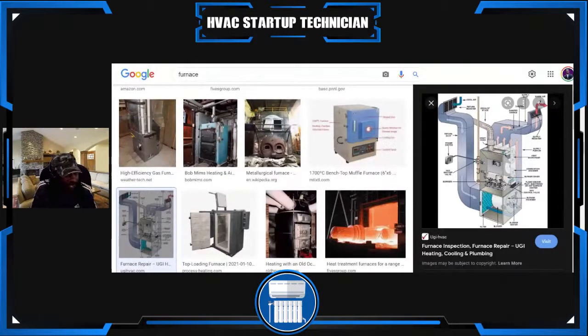And then again, you're still looking at your manual. I can't tell you guys how many times this is really important, that you look at the manual for your outdoor unit and configure this out. We're still inside though, because we still have to go back to the furnace, because the wires for the cooling outside are on our board. Remember, it's that fan. We're still talking about the fan; even though we're talking about the outside air conditioner, the fan remains the same. So we look in our book and see how much we need for cooling. If we have a 2 ton, we know we have 400.